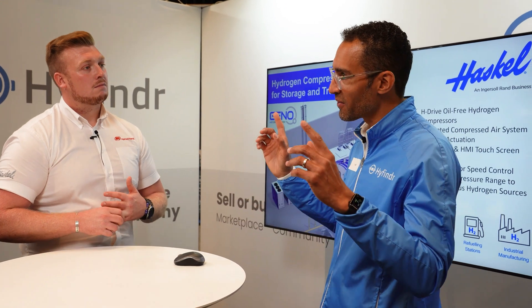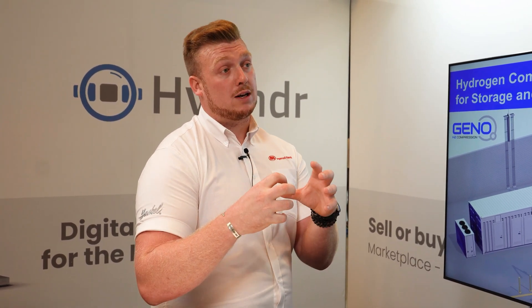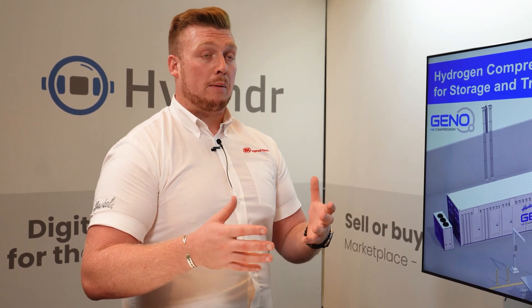I need to ask this because it's a personal question — I've actually seen one or two refueling stations out of service because of something with the compressor. Can you tell us about the reliability and any guarantees? 100%. The compressors that we supply are hydraulic, oil-free, which means when you're compressing the molecule there's no oil or moisture present. There have been historic problems where moisture gets into the system. There are lots of types — diaphragmatic, reciprocating, liquid ring — but the type we offer is very controlled and variable. All of our compressors will last for six months in service before seals need to be changed. The compressors themselves are also designed to be much more effective than many competitors, and that's part of the IP that we offer.